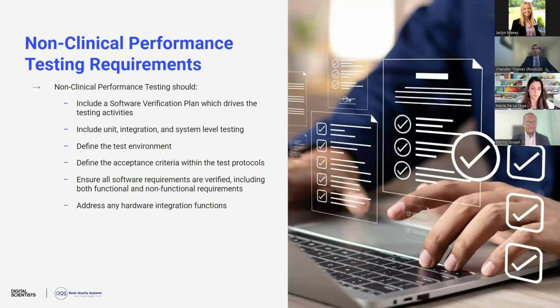The testing should also define the acceptance criteria within the test protocols to make sure that the goal and the aim of the test is clearly defined before you execute. In some cases, FDA has rejected test reports based off acceptance criteria not being defined, even if the test results were good, rather. Failure to identify test requirements and acceptance criteria means that you can't truly call the test a pass or a fail. So making sure that you have that acceptance criteria outlined before beginning testing is definitely critical.